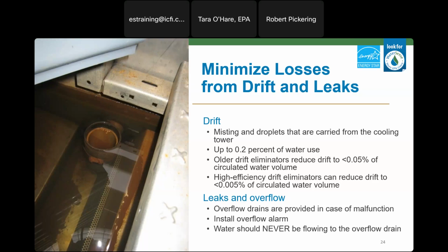This is a good thing to really monitor during daily rounds. A broken fill or float valve in a cooling tower can easily waste hundreds of thousands of gallons every day, especially if it goes unnoticed. So definitely something to check in on. In short, you should never ever see water flowing to the overflow drain. This is only meant for overflow situations. So if you see water in your overflow drain, check it out, identify the issue and correct it as quickly as you can.